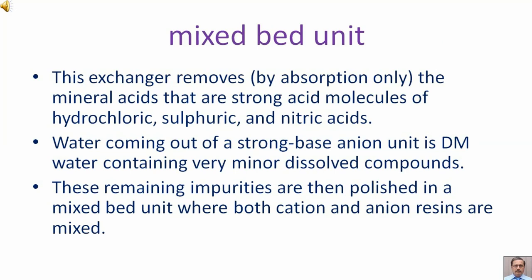Water coming out of a strong base anion unit is demineralized water containing very minor dissolved compounds. These remaining impurities are then polished in a mixed bed unit where both cation and anion resins are mixed.